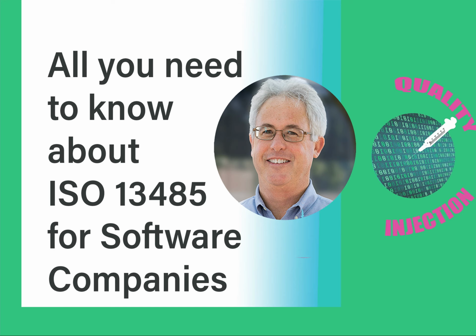In your engineering tools, your risk analysis, you can tie your risk directly to your requirements and test cases. So to be better, faster, cheaper, leverage these tools and be more efficient. Then you can send these requirements documents out for peer review, and then have those submitted to the FDA or whatever your regulatory body is. So yes, I would highly encourage folks out there to leverage tools such as Greenlight Guru or any of these sophisticated development tools. Automated unit testing, too. Back in the day, we used to have to do unit testing manually. Now you can set up automated unit testing and run it every night, and there's huge value in that.